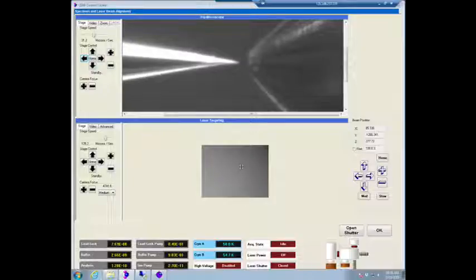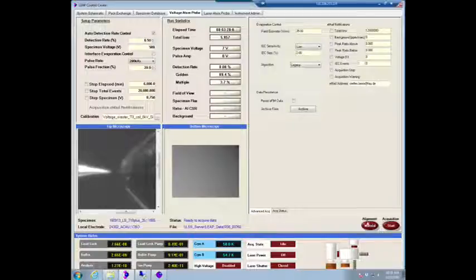So the thing with the second camera is actually it's a laser targeting camera. So it's on a piezo microstage because it needs to be aimed with, of course, a couple hundred nanometers precision because the spot is only 2 microns. So you can't move it by hand. There are coarse alignment screws, but fine alignment always has to be done in the computer, which is something that obviously didn't work out all that well. Well, the problem is it's aiming at the wrong spot. The camera is working, but the camera is not aiming at the sample. It's aiming somewhere completely different, which means the entire laser system is aiming somewhere completely different.